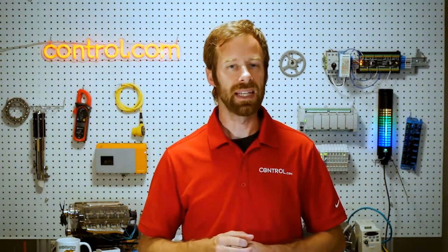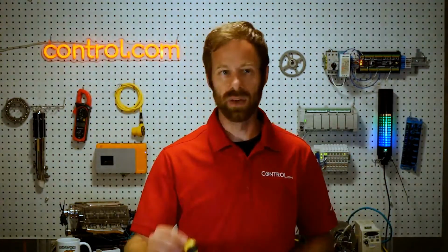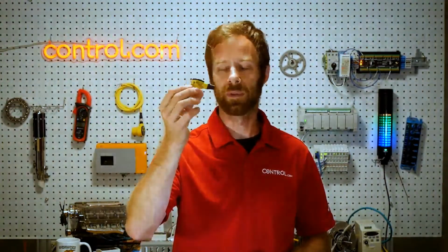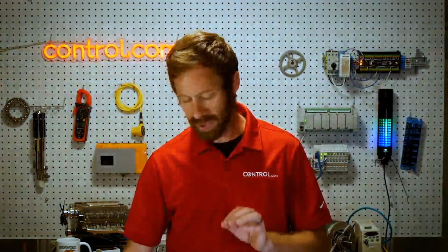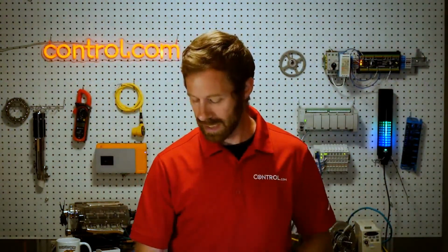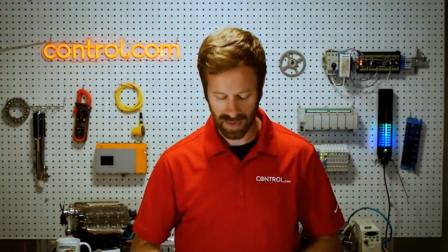But it can also, at the same time, be sending us those analog values. It is rare, but possible, to find both analog and digital sensors in the normal 3-wire type of arrangement, where the 4th wire is the analog signal and the 3rd wire is a settable discrete signal. But those, although they provide a bit more flexibility, are still fairly limited as far as sensors go.